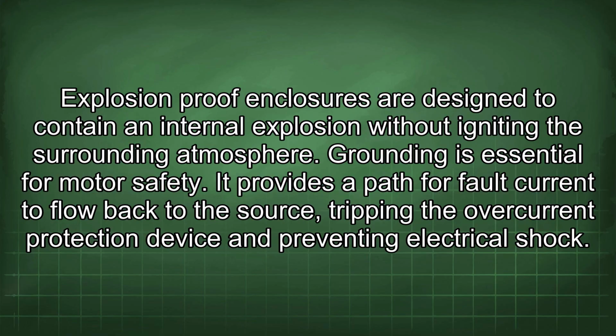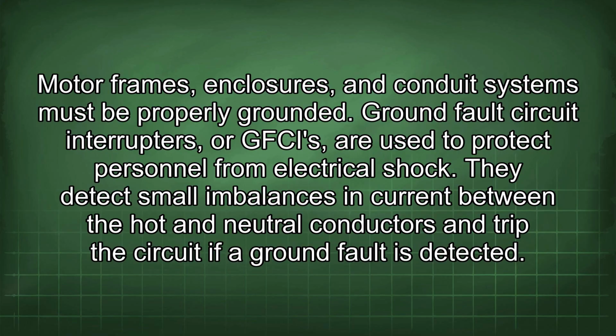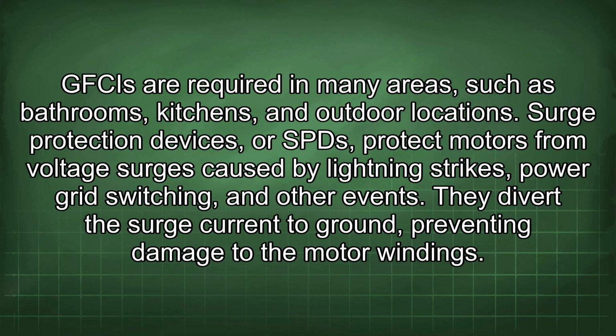Grounding is essential for motor safety. It provides a path for fault current to flow back to the source, tripping the overcurrent protection device and preventing electrical shock. Motor frames, enclosures, and conduit systems must be properly grounded. Ground fault circuit interrupters, or GFCIs, are used to protect personnel from electrical shock. They detect small imbalances in current between the hot and neutral conductors and trip the circuit if a ground fault is detected. GFCIs are required in many areas, such as bathrooms, kitchens, and outdoor locations.